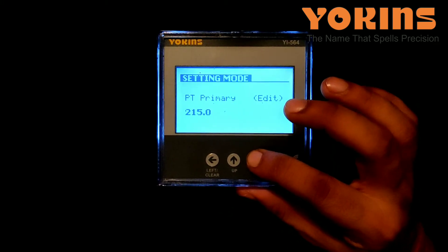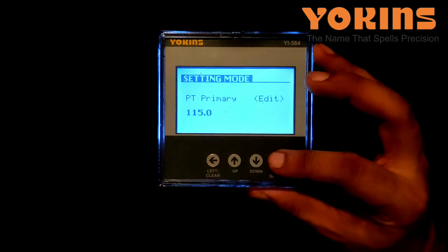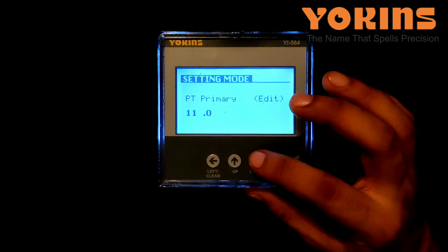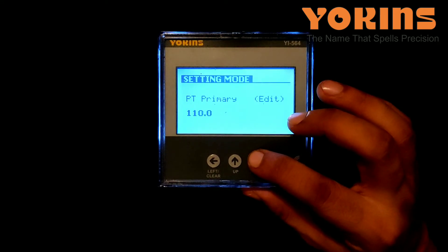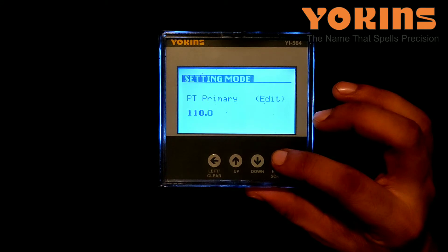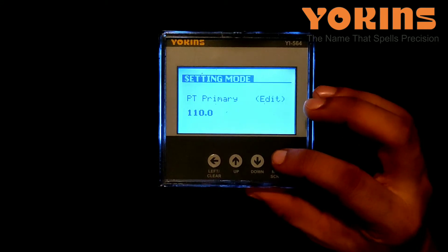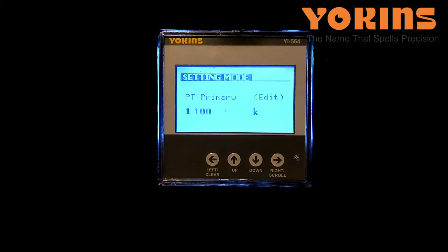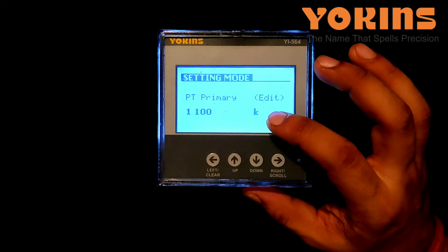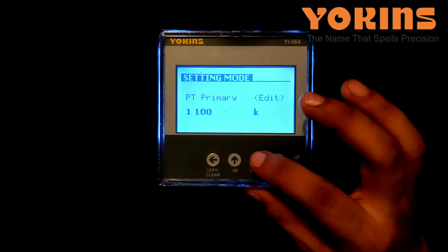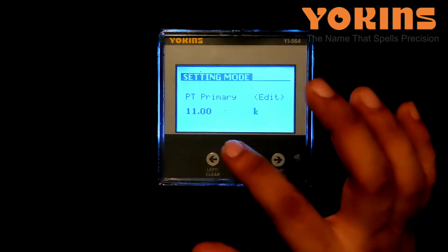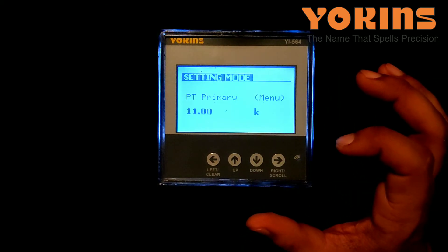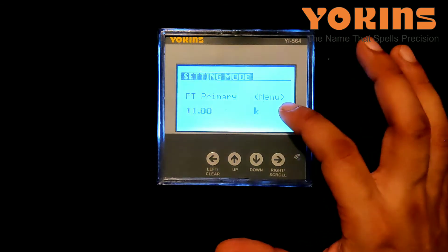We'll press the down button to change the first digit to 1, then press right button. The second digit starts blinking — no change needed. Press right button again; the third digit starts blinking. We need to change it to 0, so we press down button to make it 0. Press right button again; the fourth digit starts blinking. Press down button — the decimal will start blinking. We'll press down button once; it changes to 1.1kV. Press down again; it changes to 11kV. We'll press right button to save it.